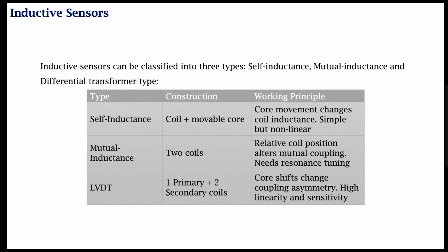Of course, we need to determine k, but that is quite trivial. That is a matter of calibration. You could find k by using a calibration routine, and once you find k, that k is not going to change. A great advantage of this approach is that it is linear. Actually, LVDT by definition is linear.